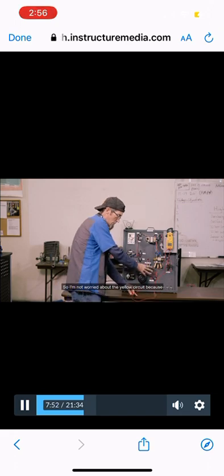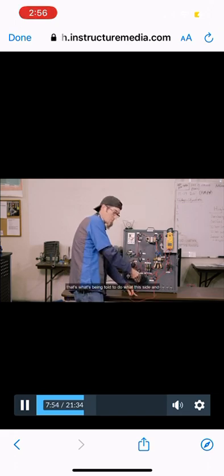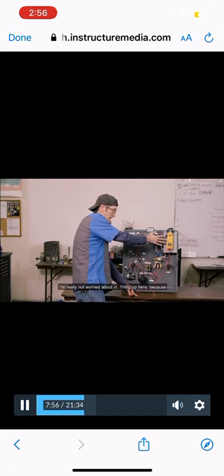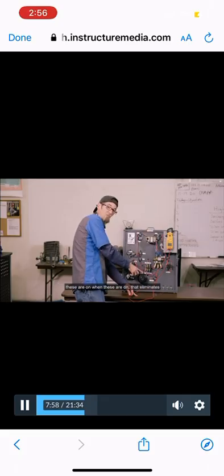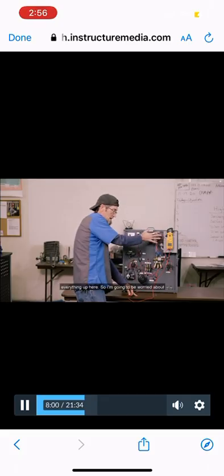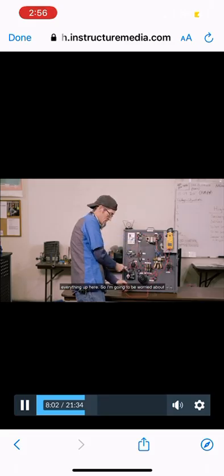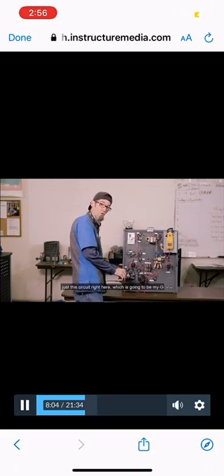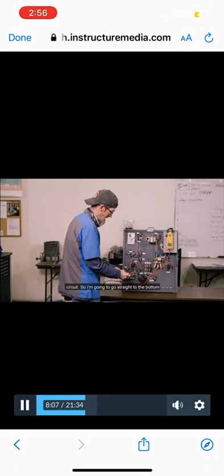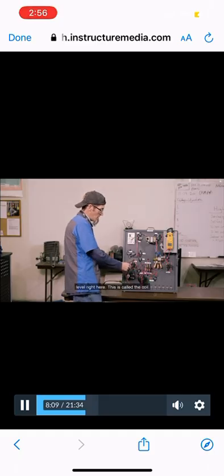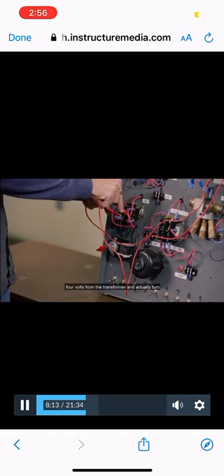So I'm not worried about the yellow circuit, because that's what's being told to do what this side. And I'm really not worried about anything up here because these are on. When these are on, that eliminates everything up here. So I'm going to be worried about just this circuit right here, which is going to be my G circuit. So I'm going to go straight to the bottom level right here. This is called the coil. And that's actually what's going to take the 24 volts from the transformer and actually turn my motor on.